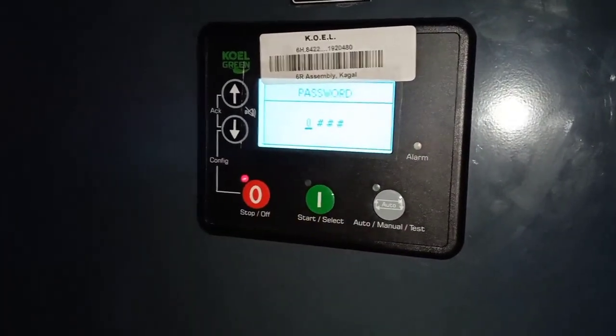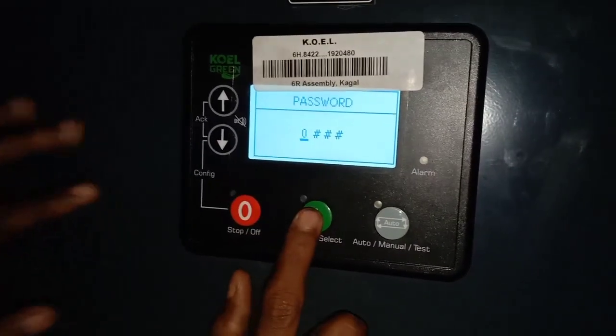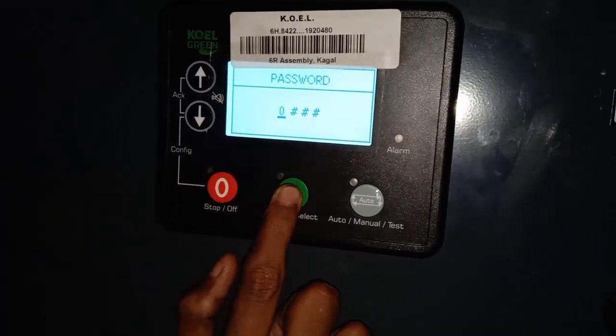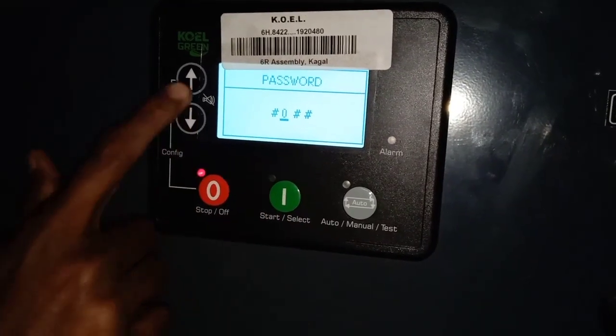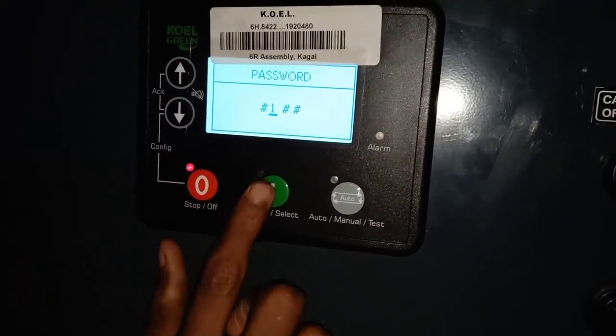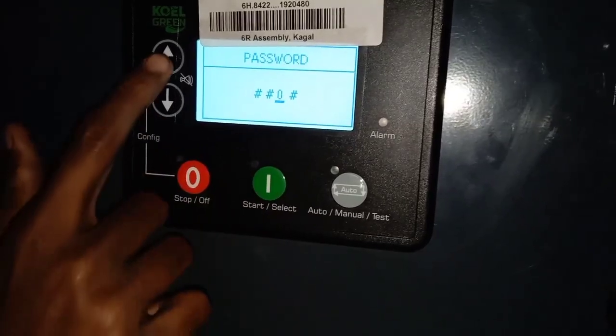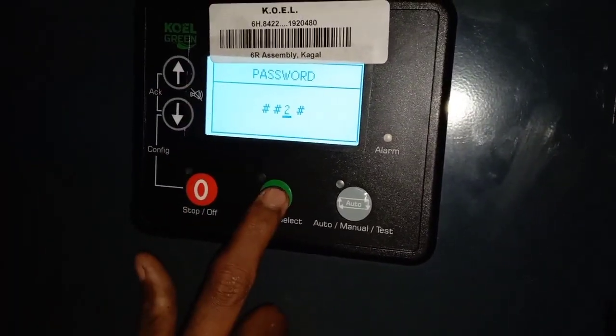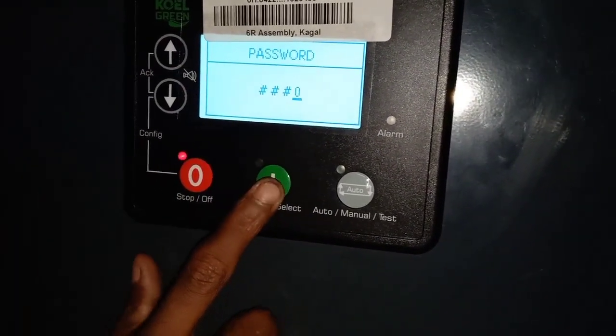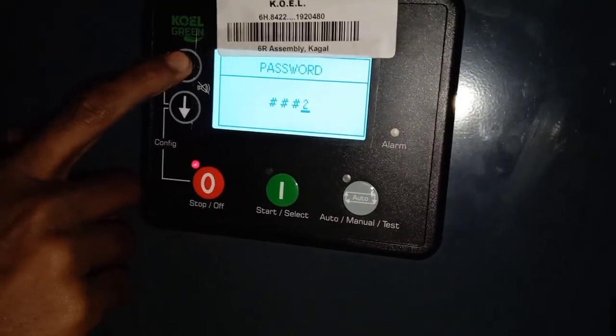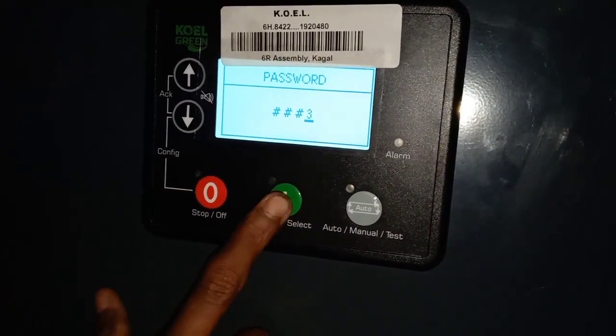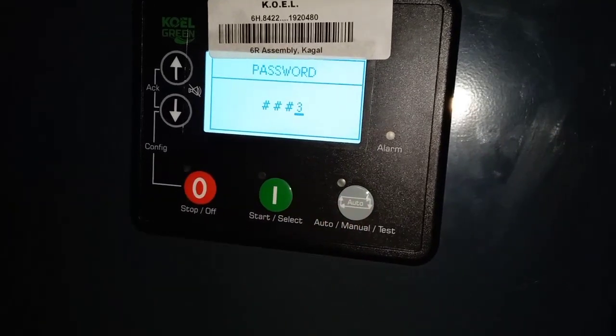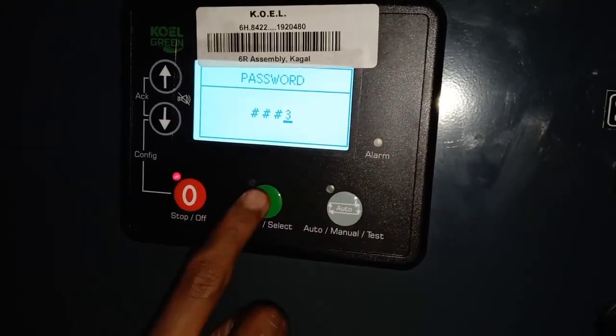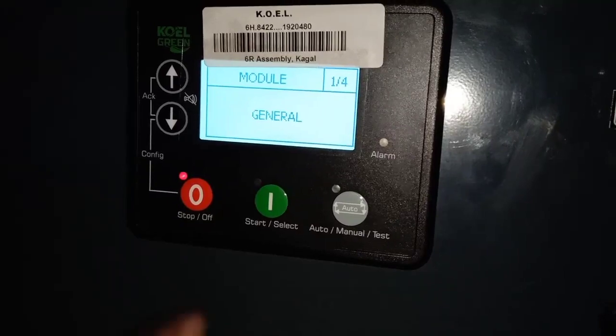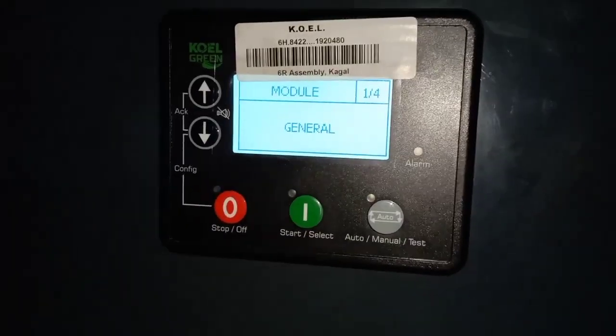Once you select write mode, it asks for a password. Please note, passwords are different from controller to controller. You may get the password from your local authorized service dealer. You can use the up and down arrow keys to enter the password. Once you enter the password correctly, press the green button to enter the settings mode. Now press the start button to enter further settings. Please note, sometimes these settings are already enabled at the factory. If not, we can check whether settings are already made or else we can change them.